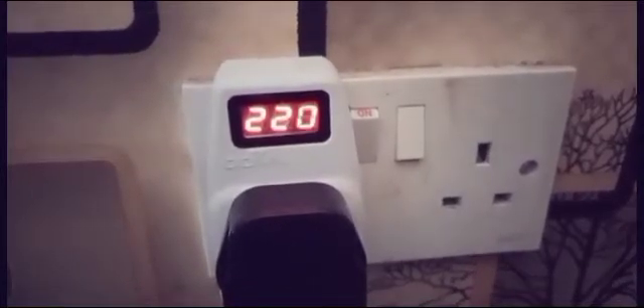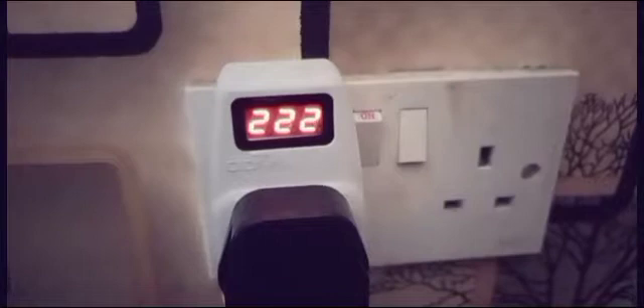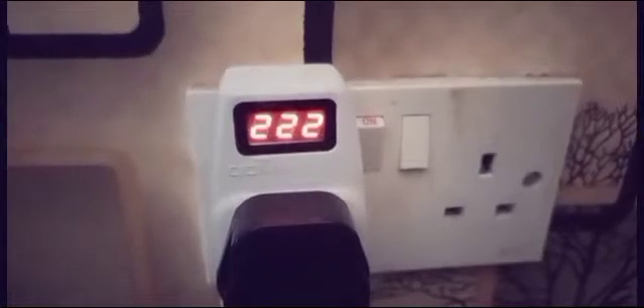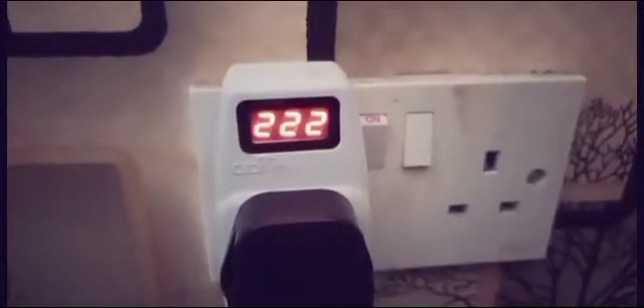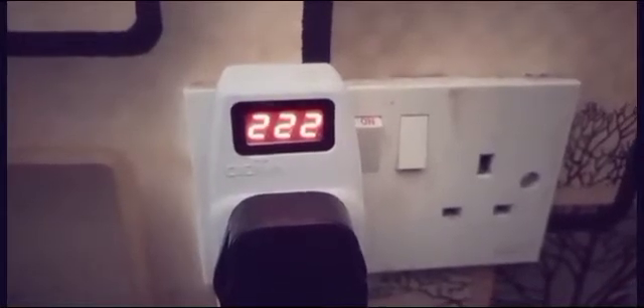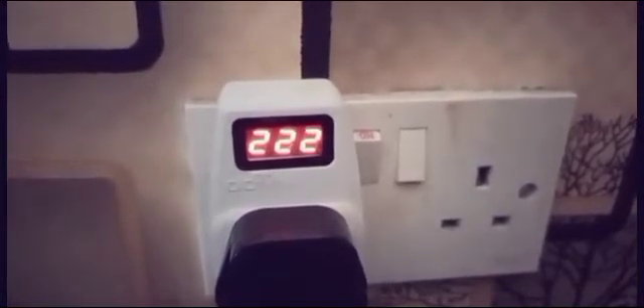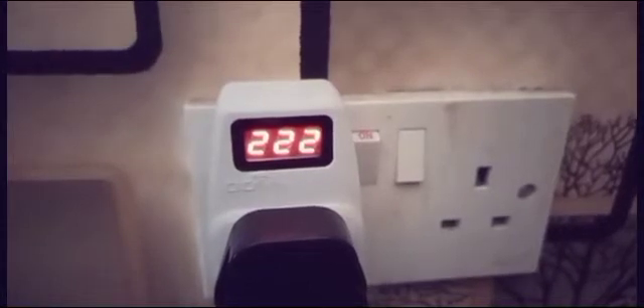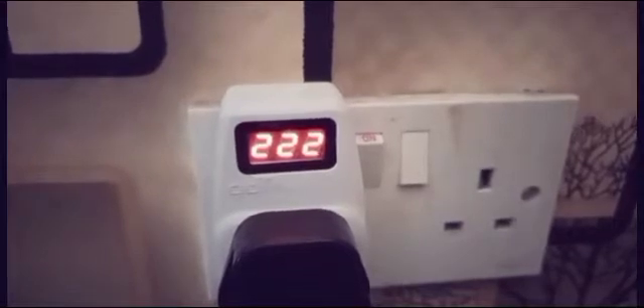I'm off-grid using a Felicity Solar 5kVA power inverter. I decided to use this voltmeter to check if what the inverter is telling me is correct. Maybe the connections in the house are affecting the voltmeter, but this is what it is reading. It's supposed to be 220 volts, but I discovered that it bounces — sometimes it gets to like 217, 214, and other times it goes over 220, like what we're seeing right now.